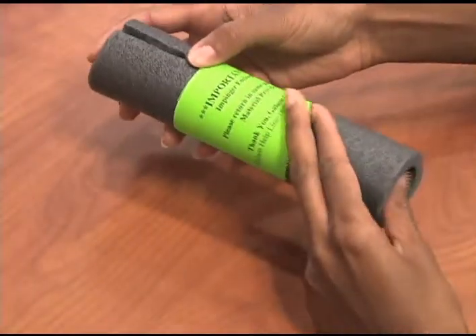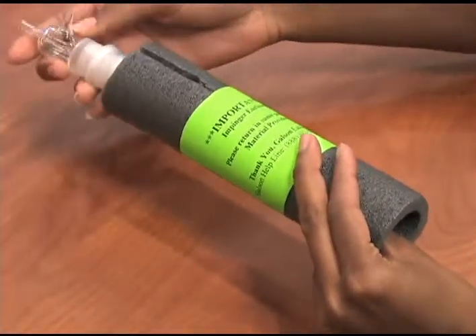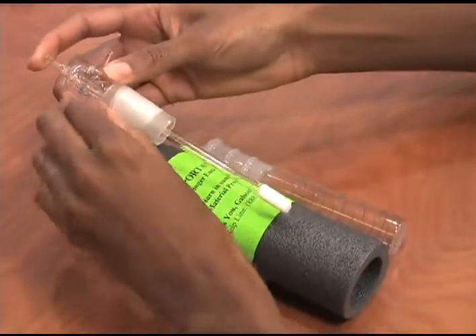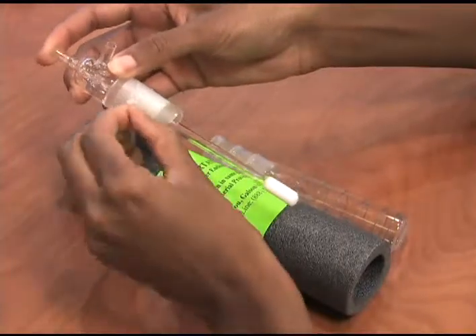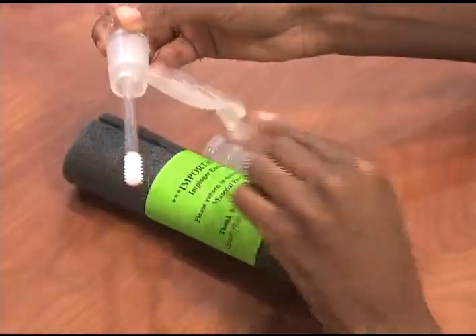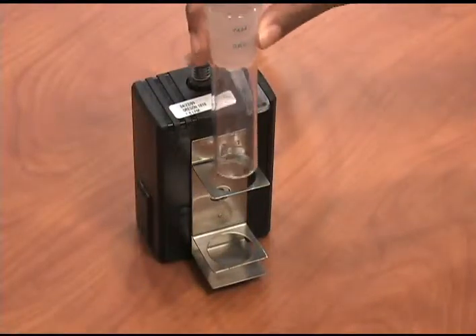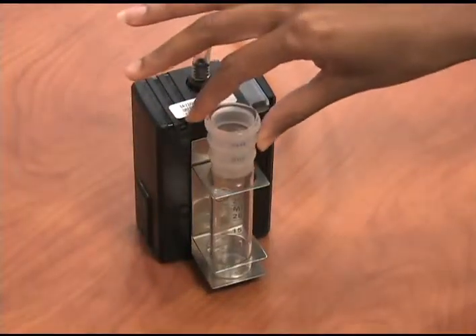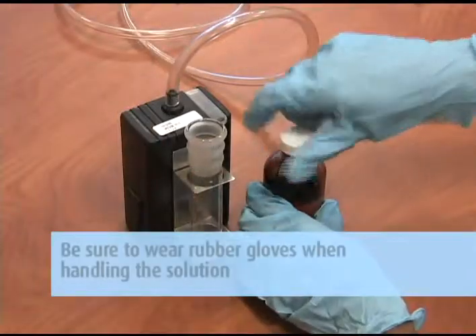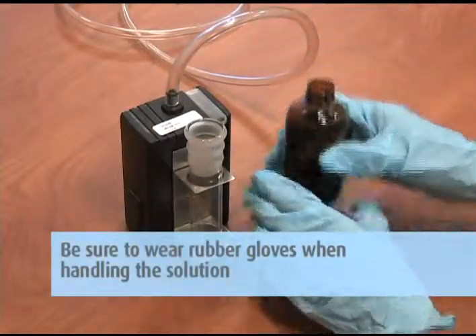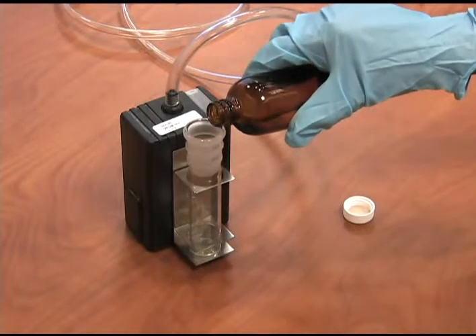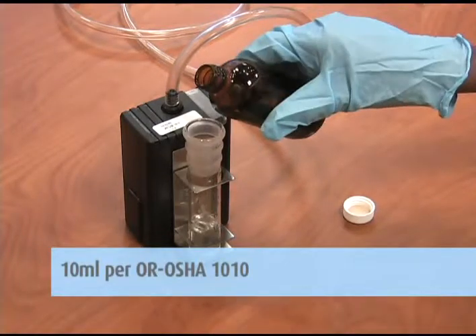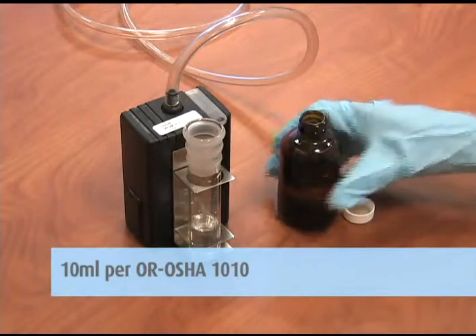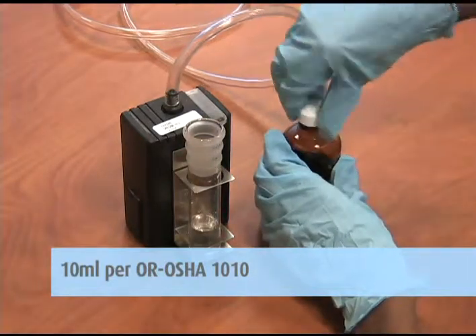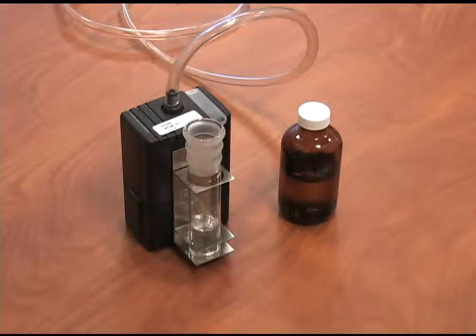Remove the impinger from the foam packing material and save the material for return shipment. Separate the impinger and remove the paraffin wax from the top portion of the impinger that prevents the impinger from fusing together. Insert the bottom portion of the impinger into the impinger holder with the units of measure visible. Be sure to wear rubber gloves when handling the impinger solution. Dispense the proper amount of impinger solution, 10 milliliters per OSHA 1010, according to the method, using the milliliter measurements on the impinger as a guide, by pouring the solution directly or using the disposable pipette provided.